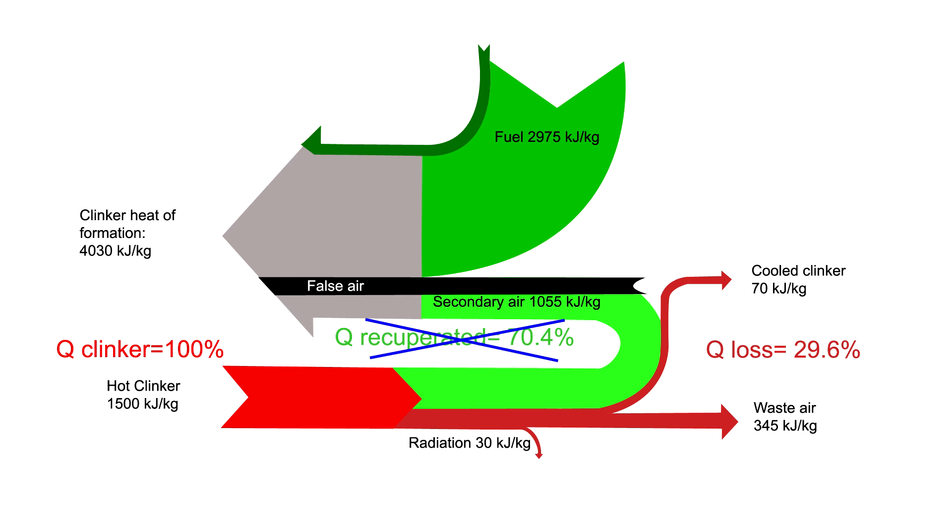And the waste air fan will have to suck out the excess hot air, which was displaced by the false air, to keep the hood pressure slightly negative. False air cannot be eliminated, but can be reduced. This is the first step to improving your cooler efficiency.